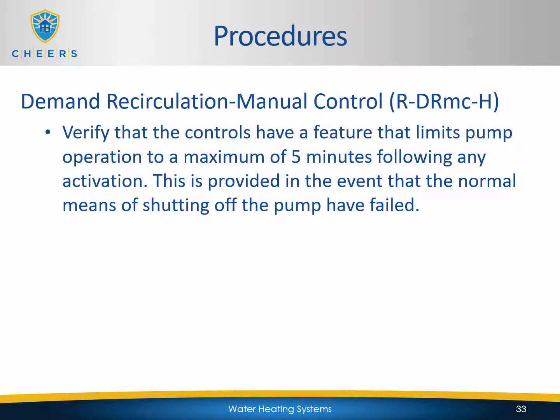You will then want to verify the controls have a feature that limits pump operation to a maximum of 5 minutes following any activation. This is provided in the event that the normal means of shutting off the pump have failed.